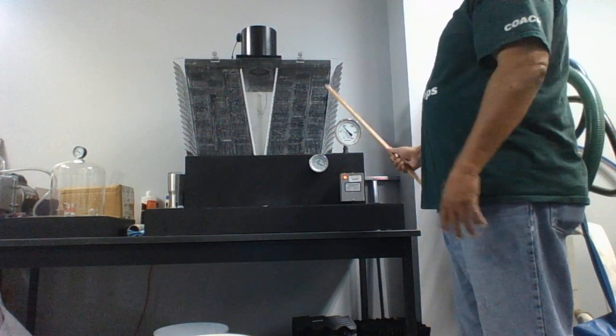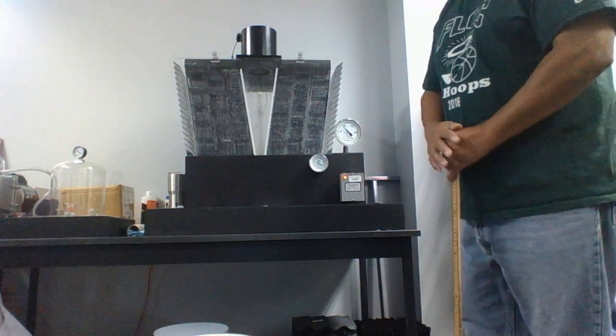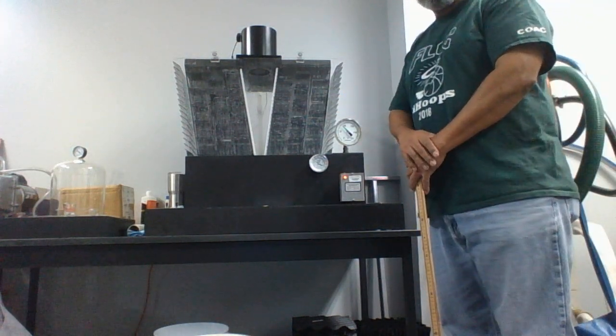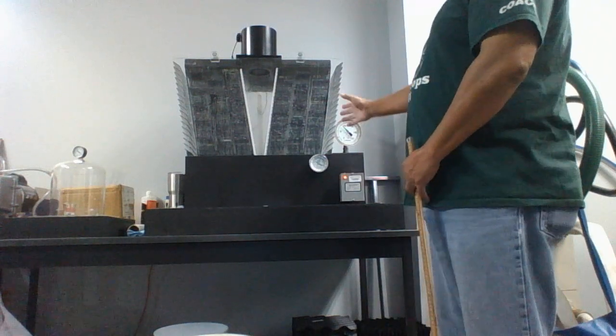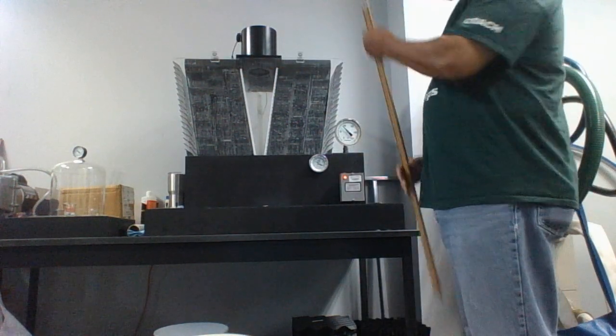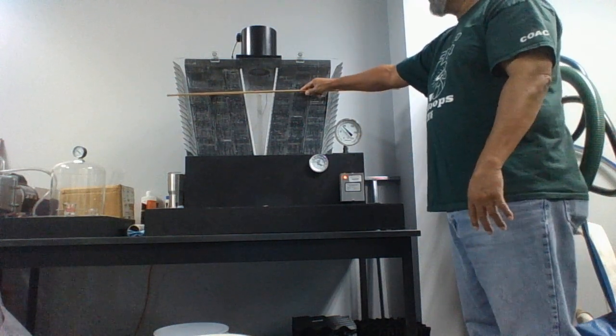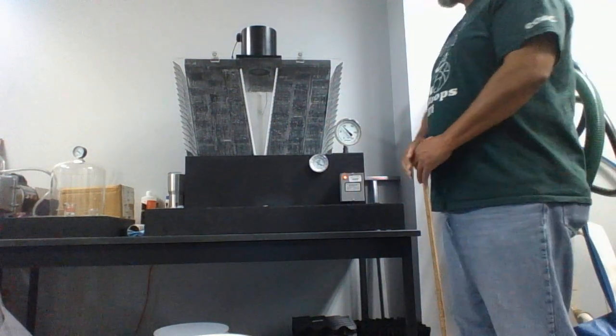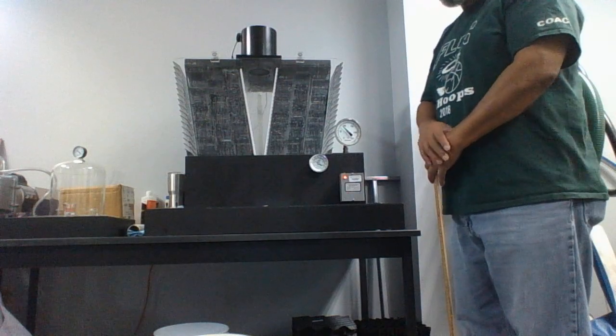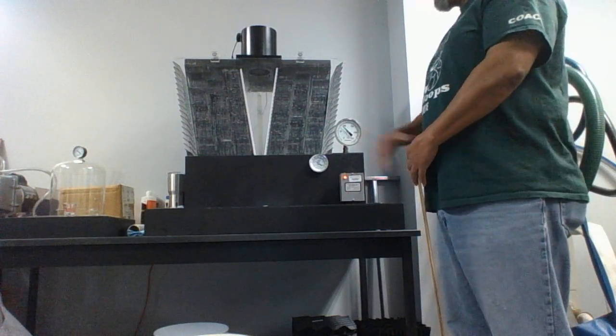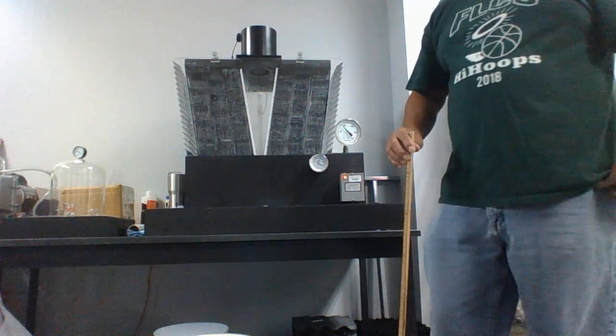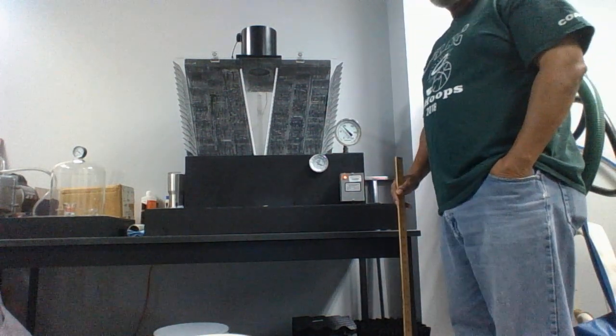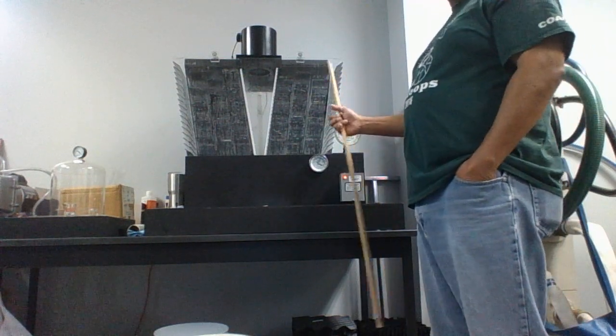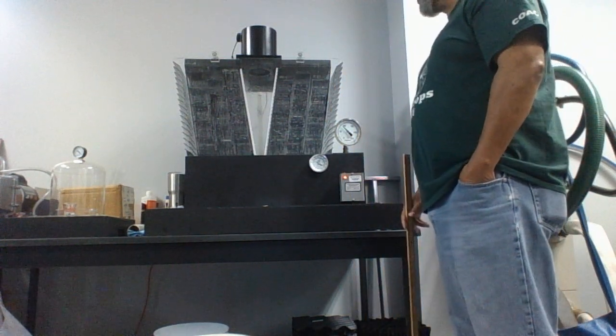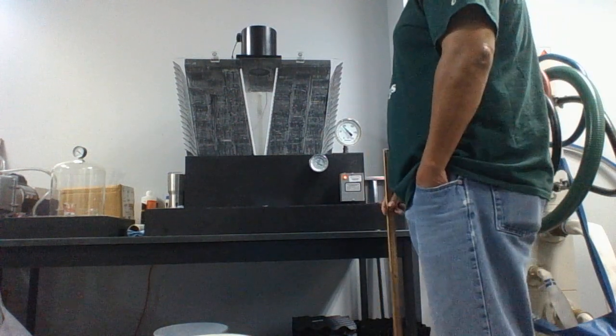What you're looking at right here is one cell of a cooling tower. I've seen as many as 13 different cells on cooling towers, so it would be what you see here 13 times in a row. We have the shroud with your fan. This would be one, and you'd have another one and another one and another one. Based on the outside temperature, your ambient temperature, if it is in the summertime with those 13 cells, I've seen as many as 10 or 11 of them running. In the winter months when it's cooler, you need less cooling, so you may have 3 or 4 of the cells running. That's determined by the unit engineer or whoever's calling the shots on that.